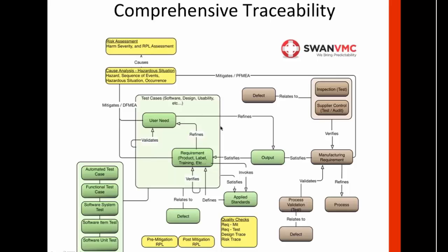So the user need is defined as a design input, which is tied out with a validation test. And these are often generally defined inputs which need engineering evaluation to refine the need into a tactical plan for the design work. The product requirements are defined as design inputs with an additional requirement that they include basically test criteria, so acceptance criteria, I should say.